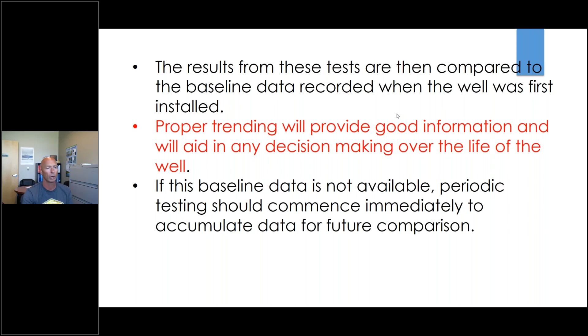If this baseline data is not available, periodic testing should commence immediately to accumulate data for future comparisons. This is where we promote, huge, having data loggers or level loggers in wells to determine pump off time and pump on time, and measure to see how far this well is actually drawing down. So, aquifer performance evaluation. Aquifer performance evaluations are necessary to establish the long-term yield of an aquifer, and should be conducted on a routine basis, especially after any changes of equipment or installation of additional wells in the same aquifer.